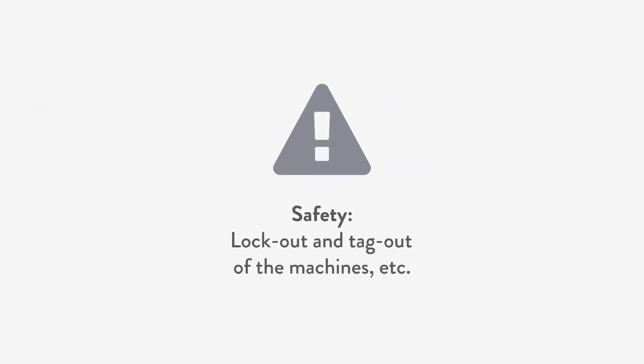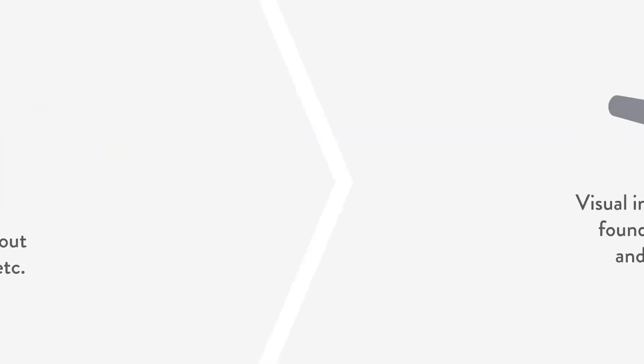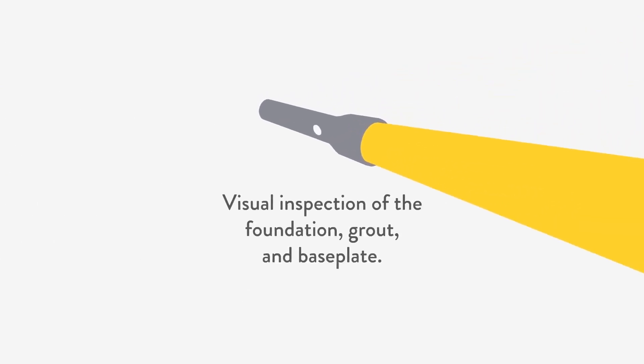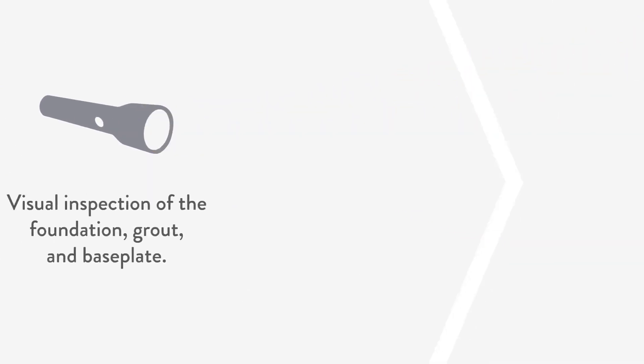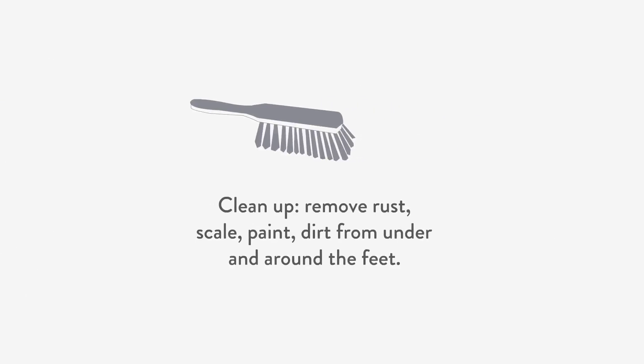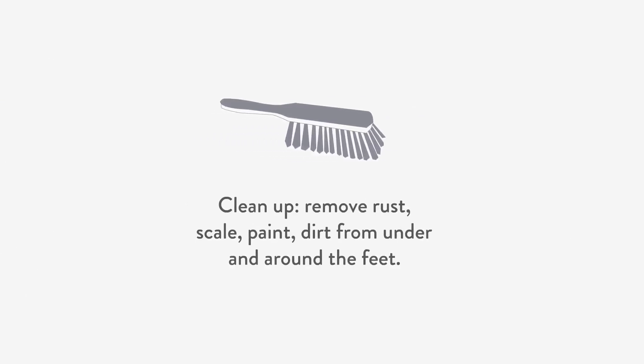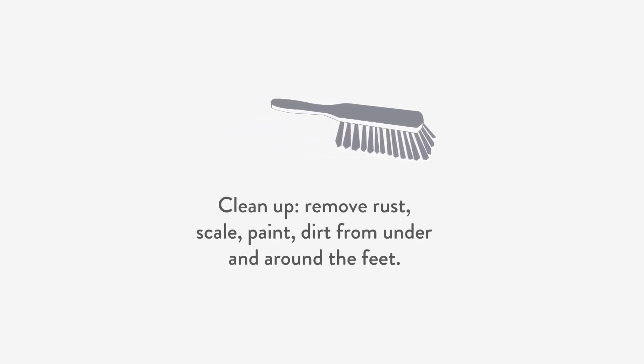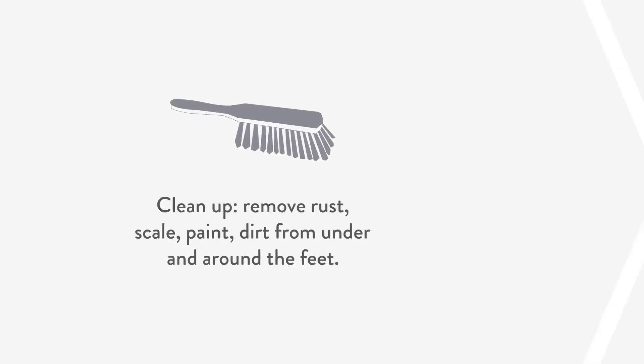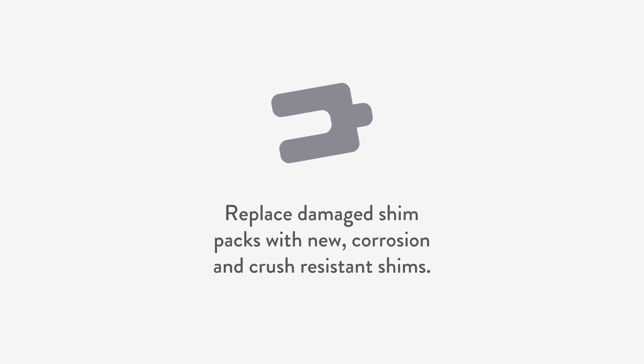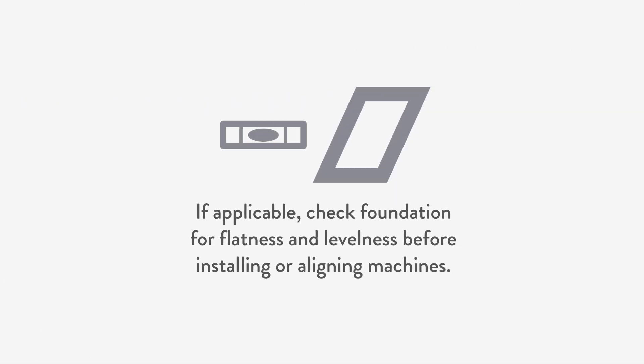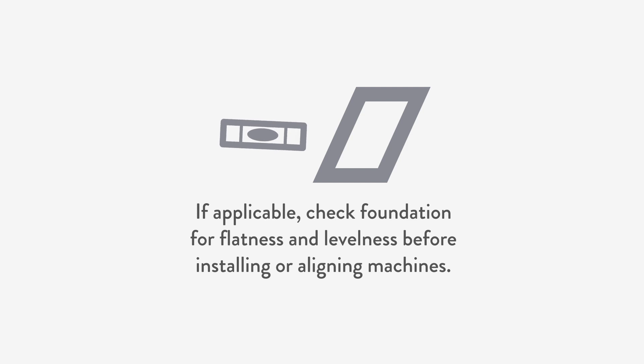Safety procedures: lockout and tag out of the machines. Visual inspection of the foundation, grout, and base plate. Cleanup: remove rust, scale, paint, and dirt from the bottom and around the feet. Replace damaged shim packs with new corrosion and crush resistant shims, filling obvious gaps under the feet if applicable. Check foundation for flatness and levelness before installing or aligning machines.